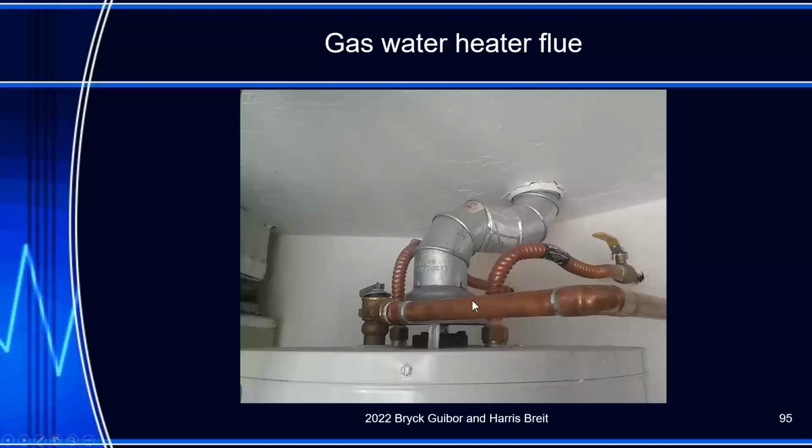So here's my pressure relief valve. Here's an elbow. Here's one down, and off it goes. I always have to have a valve here pointing the direction of the pipe, and the pipe comes out of the wall. And I don't know if the piping in the wall is copper or what it is. I have to have a 1-inch gap, why, around type B vent. Well, that's for safety for fire. Does it say it on the pipe itself? Does it right on the pipe?